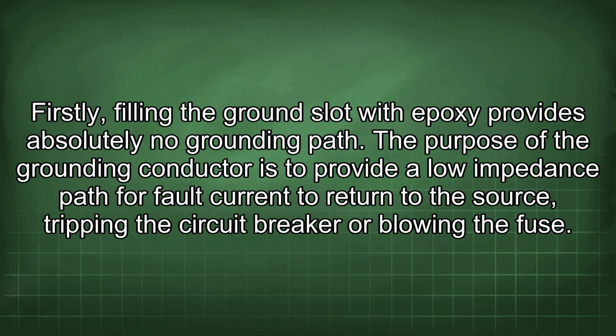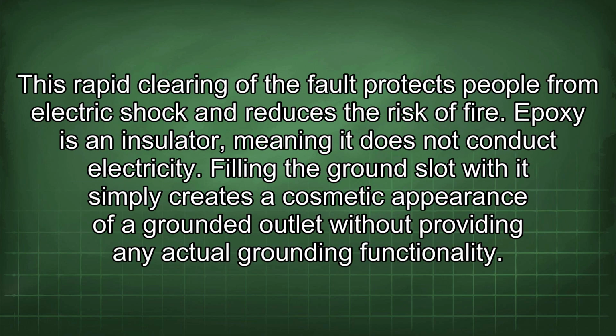Firstly, filling the ground slot with epoxy provides absolutely no grounding path. The purpose of the grounding conductor is to provide a low impedance path for fault current to return to the source, tripping the circuit breaker or blowing the fuse. This rapid clearing of the fault protects people from electric shock and reduces the risk of fire. Epoxy is an insulator, meaning it does not conduct electricity. Filling the ground slot with it simply creates a cosmetic appearance of a grounded outlet without providing any actual grounding functionality.